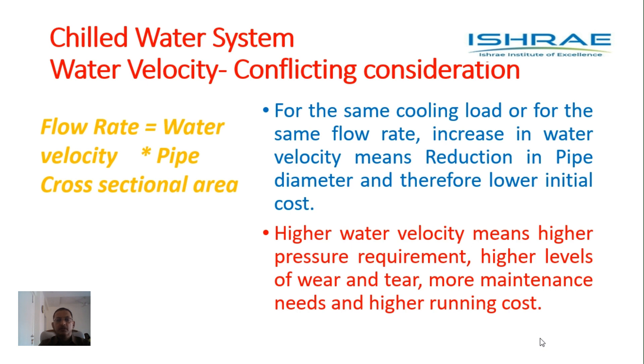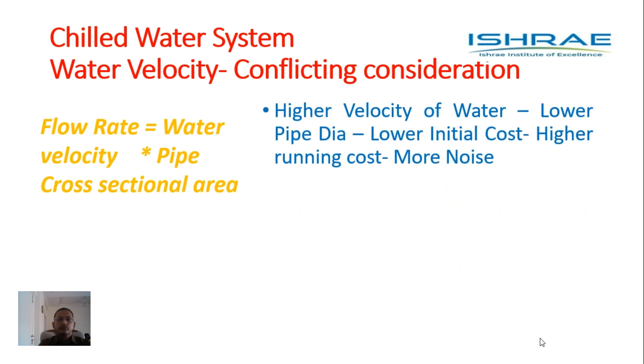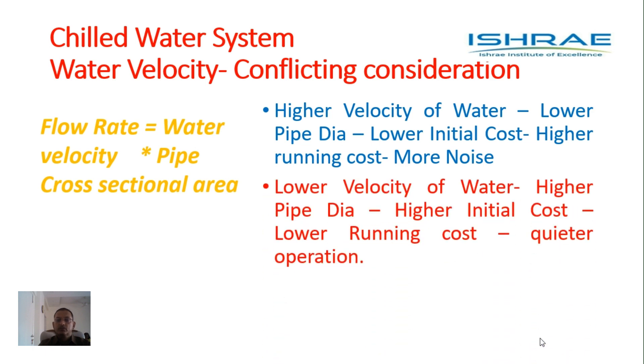It is for us to decide which one we want or where we make a compromise. Higher velocity of water leads to lower pipe diameter and lower initial cost, but it also leads to higher running cost and more noise. Lower velocity of water, on the other hand, leads to higher pipe diameter and higher initial cost, but lower running cost and quieter operation.